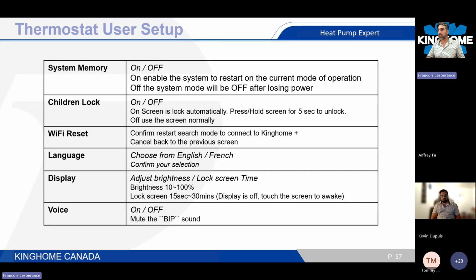Still in the user setup, there's a system memory on-off. Basically, if you set it to off and you lose power to the system, or you open the furnace panel and the power goes off, then when you reapply power, the system will go into off mode. If system memory is active, then it will go back to the last mode the system was using. So if it was in heat mode, then it will be in heat mode.